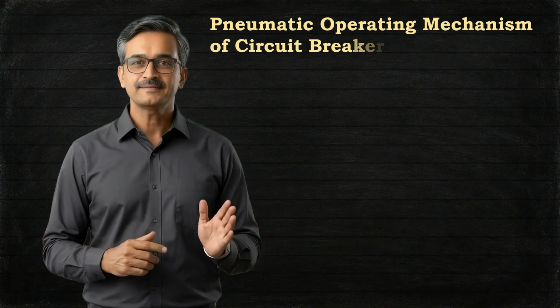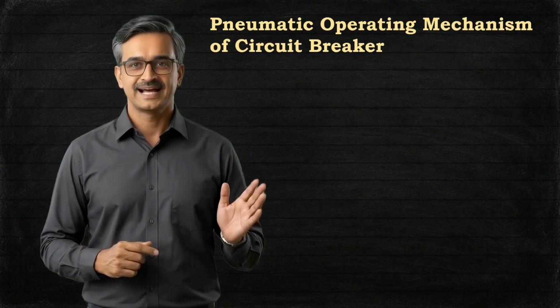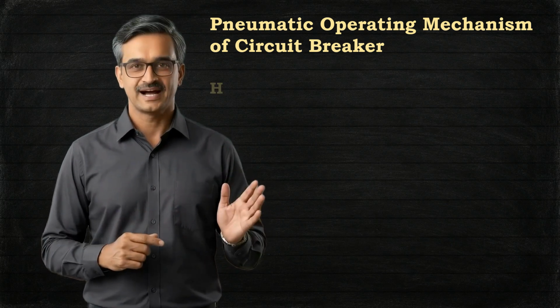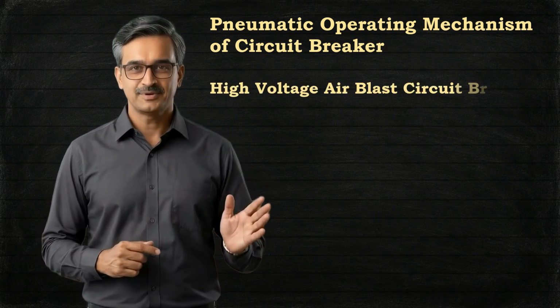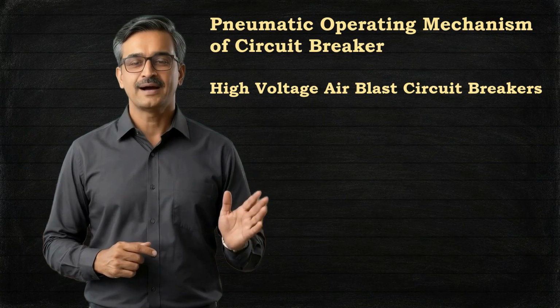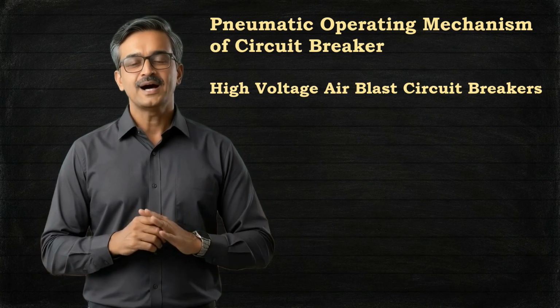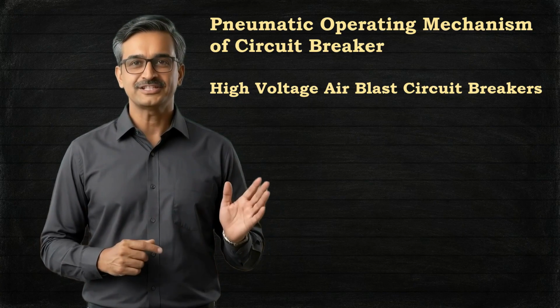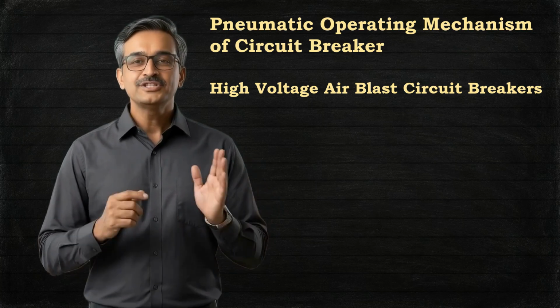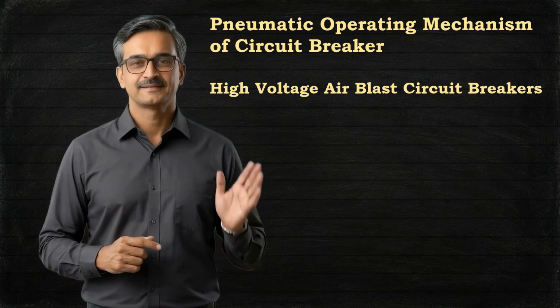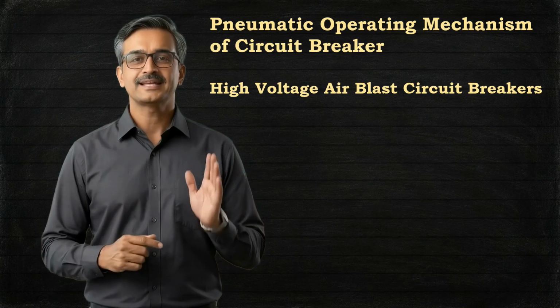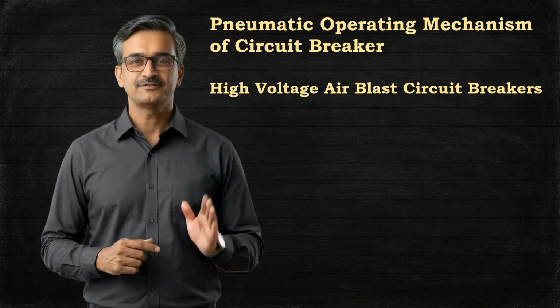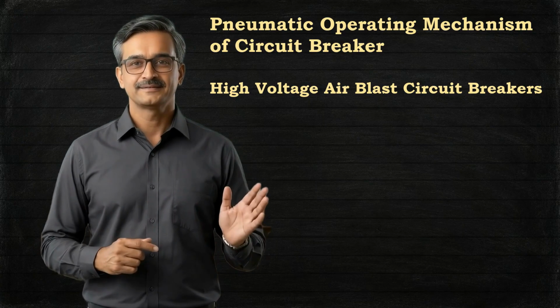Pneumatic operating mechanism of circuit breaker. A pneumatic operating mechanism is mainly used in high voltage air blast circuit breakers. Although high voltage air blast circuit breakers are no longer used in modern power systems because of their huge size and complex mechanism, they are also not maintenance-free because they require frequent periodic maintenance.